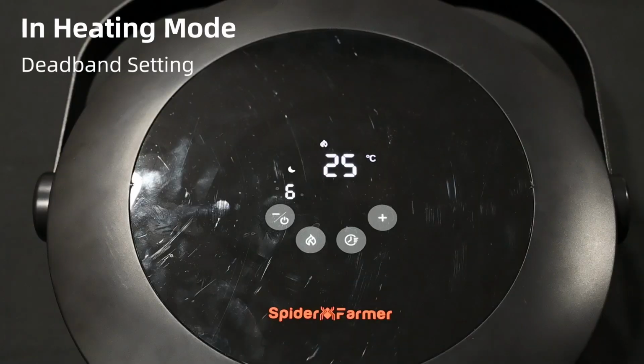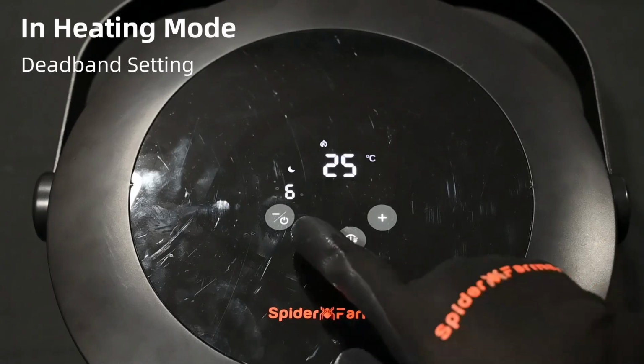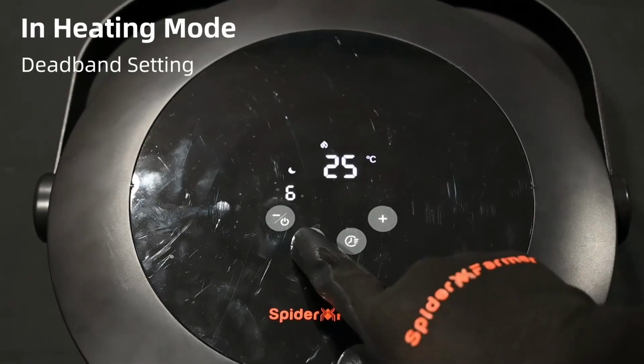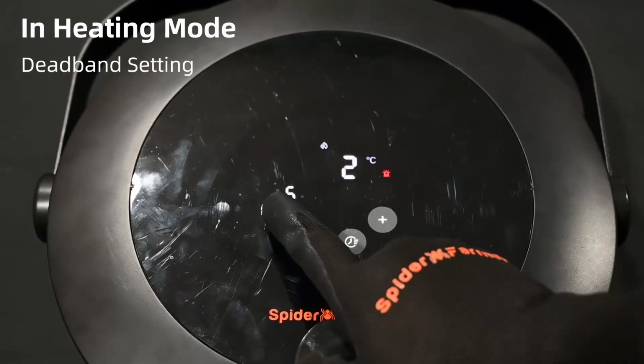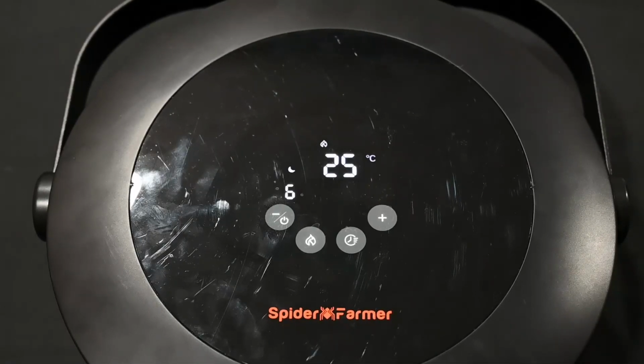To avoid frequent automatic on or off cycles, you can set a 1 degree C range for more precise temperature control. The heater will stop operating when the temperature reaches the upper limit, e.g., 26 degrees C plus 1 degree C equals 27 degrees C, and will restart when it drops to the lower limit, for example, 26 degrees C minus 1 degree C equals 25 degrees C.